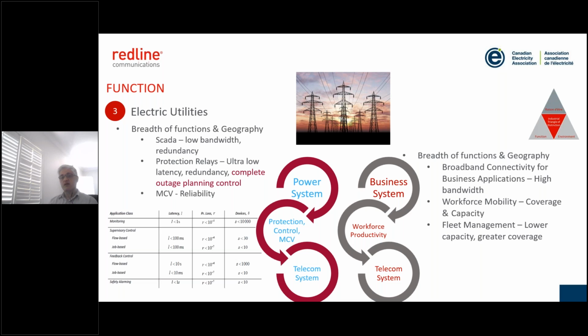One thing non-OT folks sometimes forget is the complete control of outage planning. If you have a nuclear station connected to your transmission grid, you cannot have the teleprotection links down on that infrastructure. You cannot do any maintenance on the communication infrastructure that supports protection and SCADA for that kind of generation station without properly planning it.